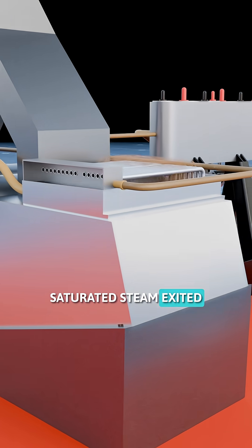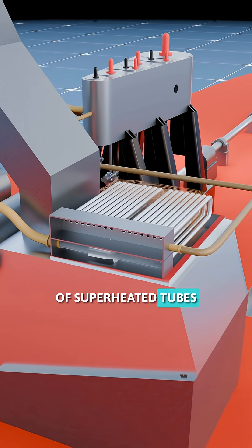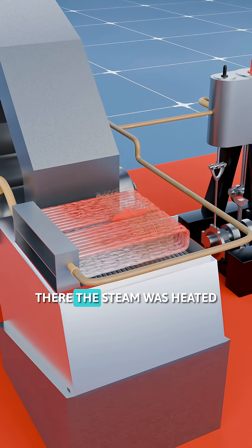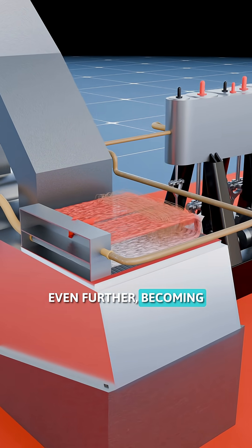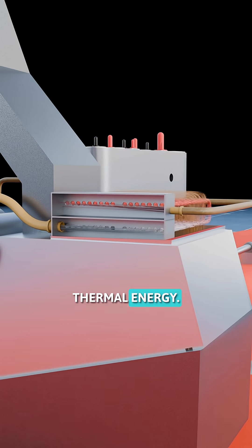Saturated steam exited from the top of the steam drum and passed into a set of superheater tubes positioned directly in the path of the hot exhaust gases. There the steam was heated even further, becoming superheated steam which contained more thermal energy.